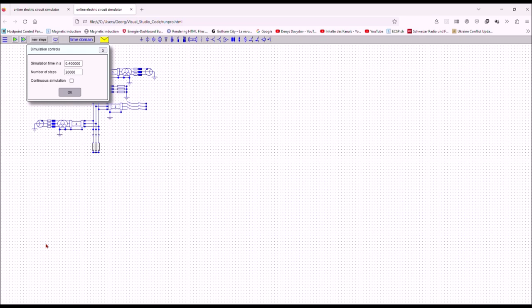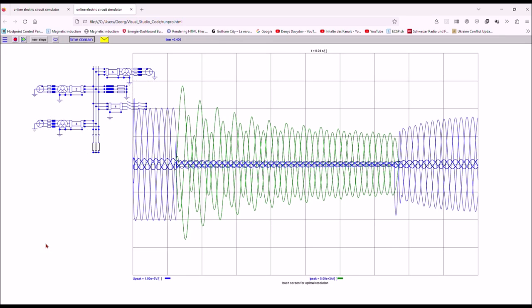It is a little bit less responsive because I have much more steps. And here you see the result. Again, voltage before short circuit, then short circuit current, and then recovery voltage across the breaker.